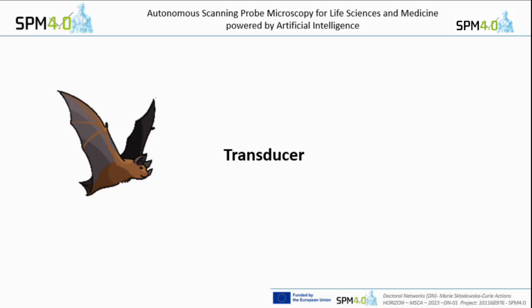I was just asking, is screaming in the range of something that works? No. Screaming is in the audible range, which is up to 20 kilohertz. And this one is 1 megahertz. So there's no interaction between both. You will only see interference if you have something in the same frequency range, a vibration, which does not happen in the normal way. Only if you have two ultrasound devices at the same place.